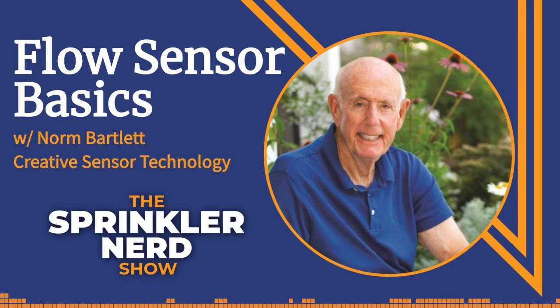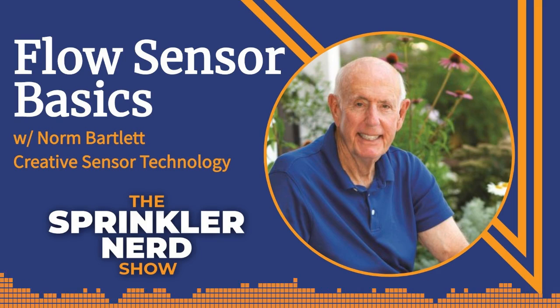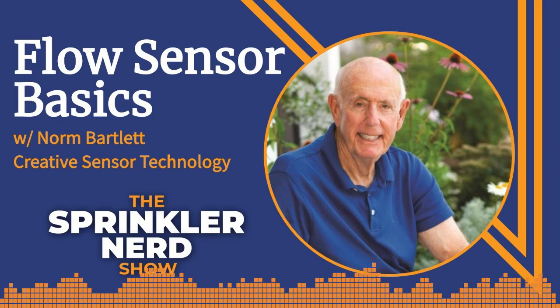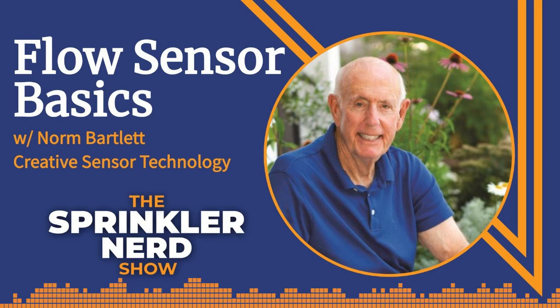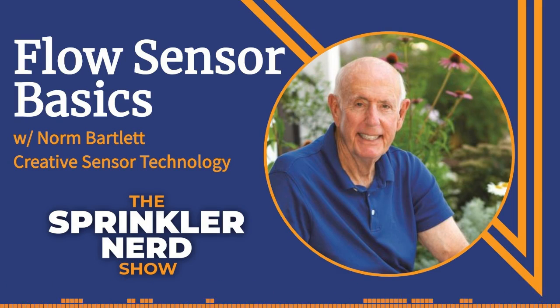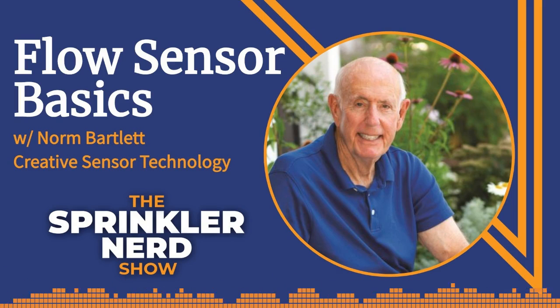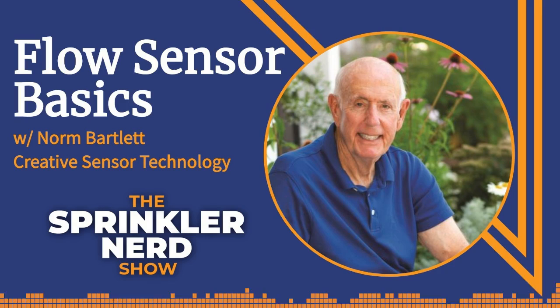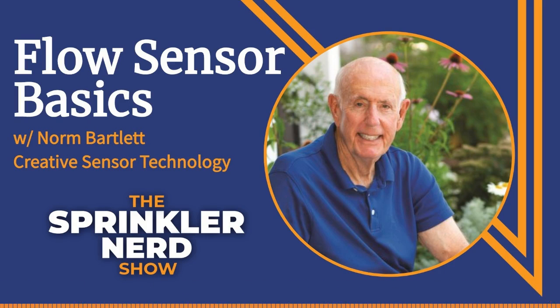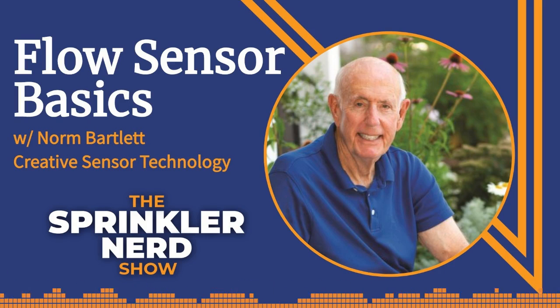Gotcha. Let's talk about that for a second. What is it about sensors of the past that either made them not able to read it or less efficient? Well, basically, any meter, nothing measures down to zero. Anything that has moving parts, anything that has a magnetic field or sheds vortices or does anything else has a bottom end where there just isn't enough energy in the water to be, in practical terms, able to be read.